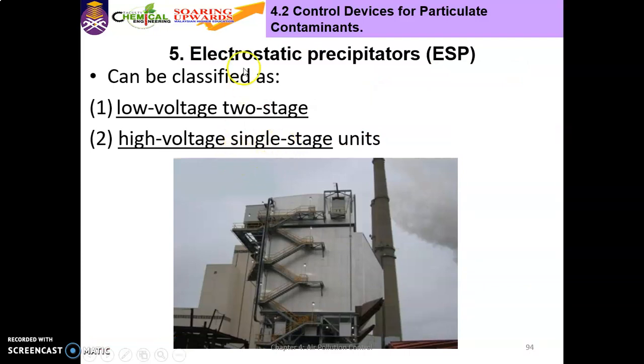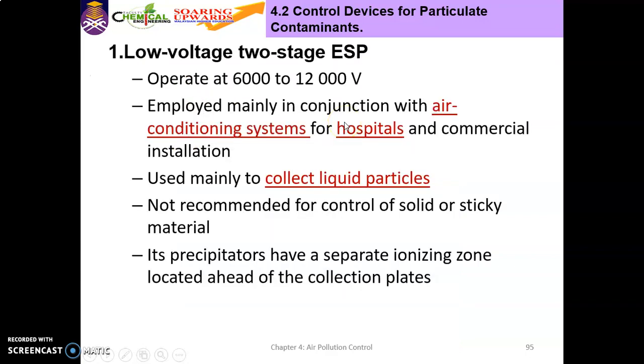okay. Equipment number 5 is the electrostatic precipitator. So the electrostatic precipitator has two types: the low voltage 2-stage and high voltage single stage units. Electrostatic precipitator also, of course, uses voltage as the source of energy. So it is employed mainly in conjunction with air conditioning systems for hospitals and also commercial installations. It can be used mainly to collect liquid particles and is not recommended for control of solid or sticky materials.